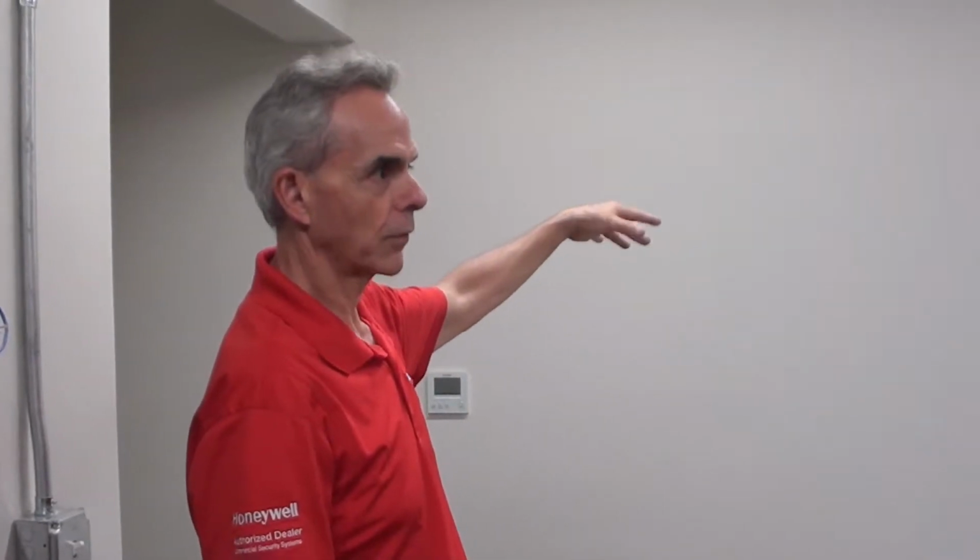It's going to tell you which floor the sprinkler riser is. Now, with the sprinkler system, it's all coming up the north stairwell. So it's going to say 10th floor or 6th floor or whatever, water flow. A water flow alarm is not silenceable. That's per the fire code. So if a sprinkler head goes off, you're not going to be able to silence it until somebody shuts the water off to it.